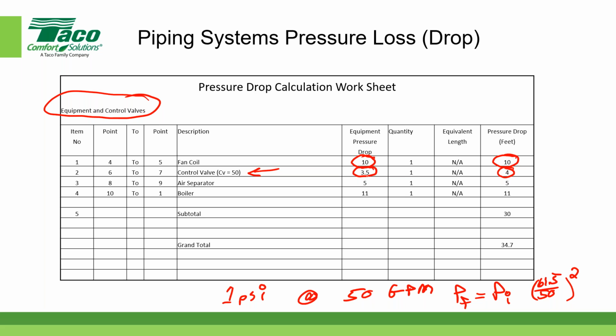I want to give a shout out to Stanley. He mentioned in the question things, the benefit of CV is to allow the user to calculate the valve pressure drop at flows other than the CV flow. Yeah. Which is what you just did. Well, so yeah, that's great stuff. Shout out to Stanley. Now here is the air separator. You get that from the manufacturer. The boiler, you get that from the manufacturer. And you add up all those numbers.